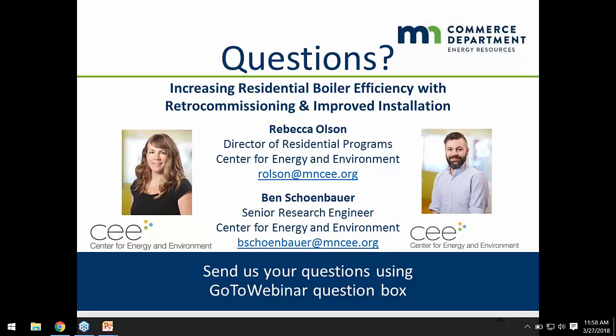Yeah, it's a good question, and we've heard that as well. Looking at these indirect boilers, in this study and a previous study that we did, I've been able to look at a handful of these different systems. So our sample size isn't huge, but it's something like 10 indirect or DHW provided by boiler systems, that range from brand new to 5 years, 7 years old. And they all perform similarly to the plot that I showed for the example site. Nothing really indicates that there's significant reduction in performance, but given that there's only a 7-ish year time span, maybe something isn't showing up, or there might be durability concerns. So we didn't look specifically at that, but we don't see a ton of evidence that there's a lot of degradation going on in these systems.